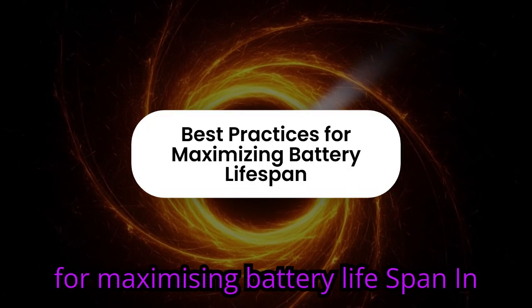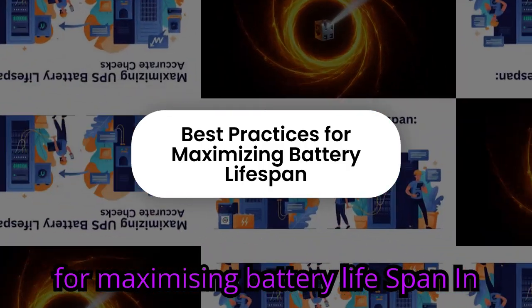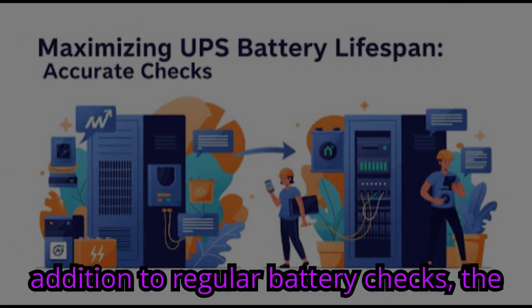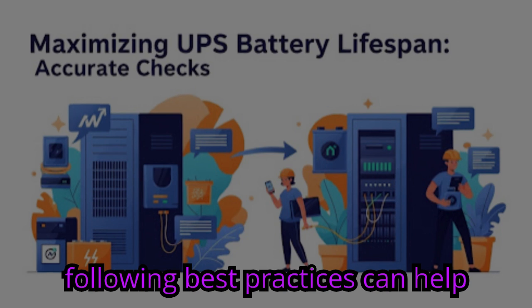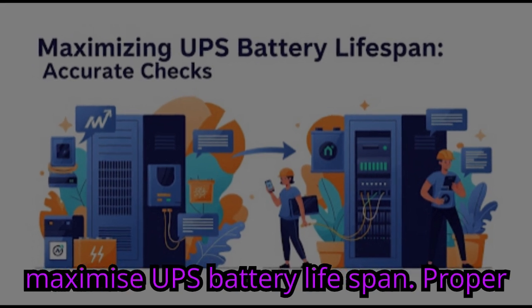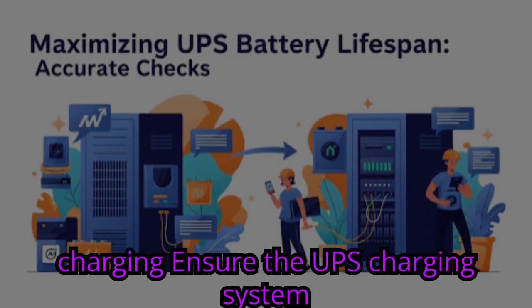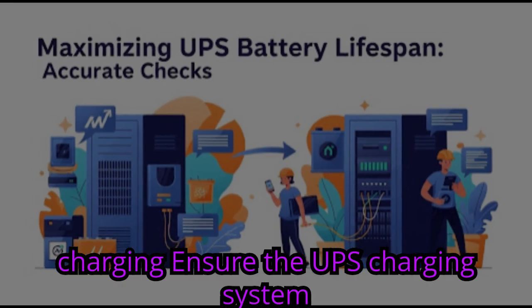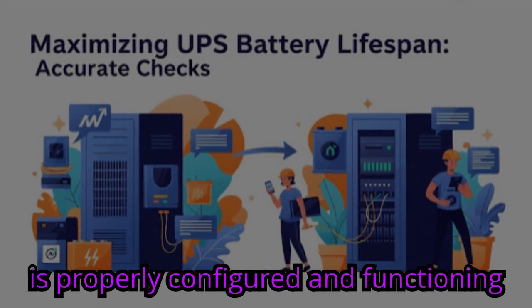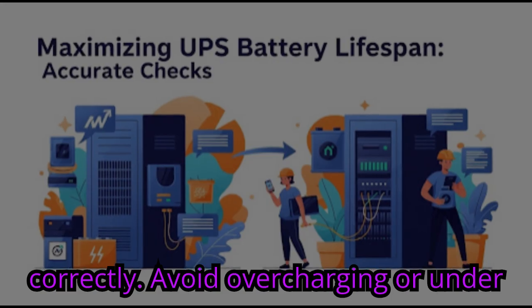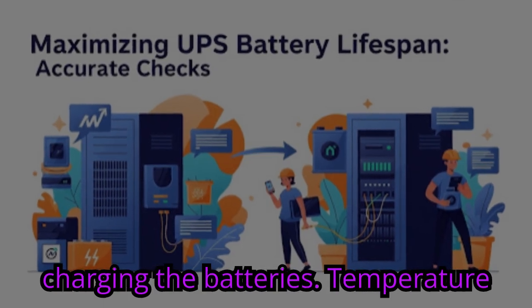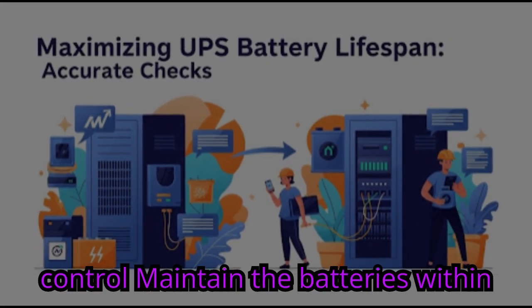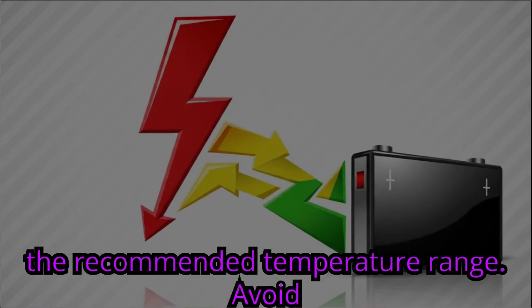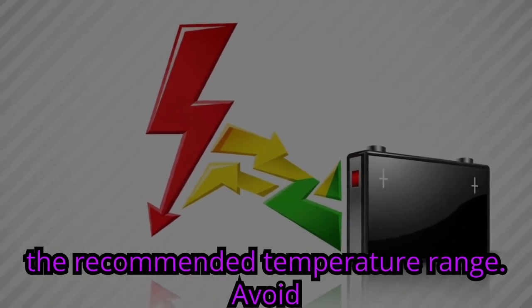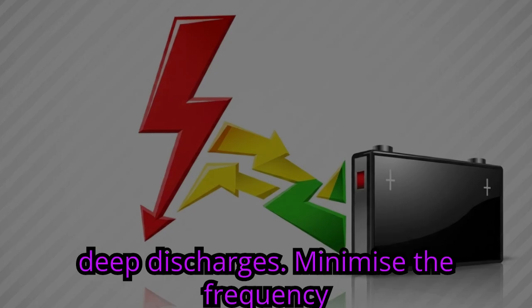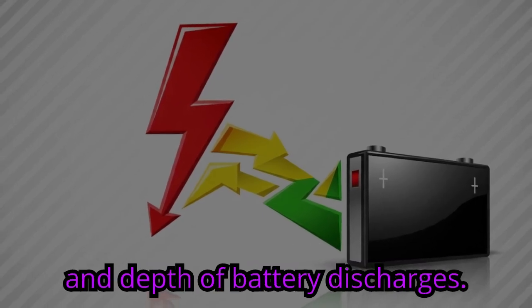Best practices for maximizing battery lifespan. In addition to regular battery checks, the following best practices can help maximize UPS battery lifespan. Proper charging. Ensure the UPS charging system is properly configured and functioning correctly. Avoid overcharging or undercharging the batteries. Temperature control. Maintain the batteries within the recommended temperature range. Avoid deep discharges. Minimize the frequency and depth of battery discharges.